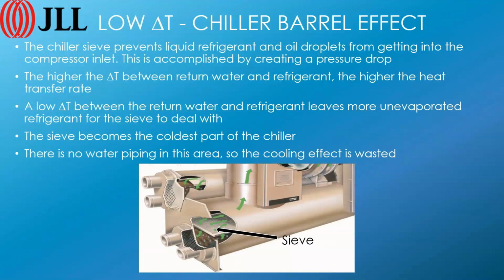Right down at the bottom, you can see something called a sieve. That sieve looks like it's a perforated metal plate. Looks like a colander, and it's there to take any liquid on the downstream or the underside, whether it's oil or liquid refrigerant, and flash it, atomize it basically. If it's oil, it just atomizes it into a vapor. If it's liquid refrigerant, because there's a pressure drop, it turns it into gas. That sieve is not in the water stream. No water is in contact with that ever.